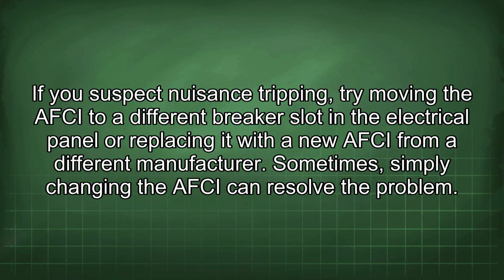If you suspect nuisance tripping, try moving the AFCI to a different breaker slot in the electrical panel or replacing it with a new AFCI from a different manufacturer. Sometimes, simply changing the AFCI can resolve the problem.